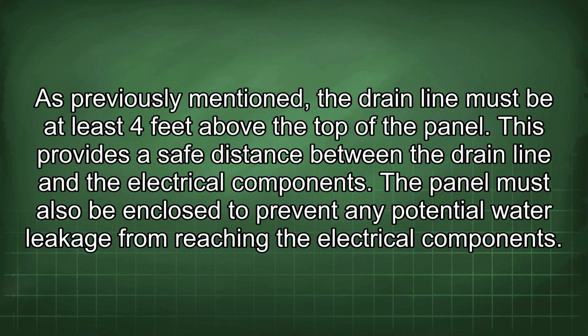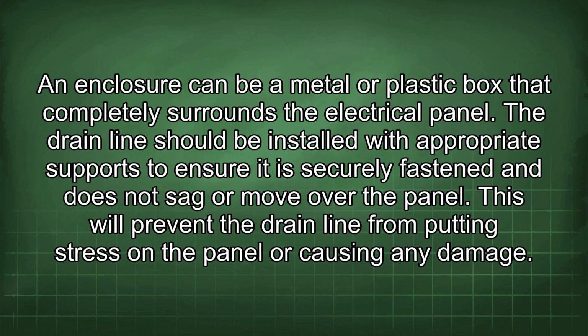This provides a safe distance between the drain line and the electrical components. The panel must also be enclosed to prevent any potential water leakage from reaching the electrical components. An enclosure can be a metal or plastic box that completely surrounds the electrical panel. The drain line should be installed with appropriate supports to ensure it is securely fastened and does not sag or move over the panel. This will prevent the drain line from putting stress on the panel or causing any damage.